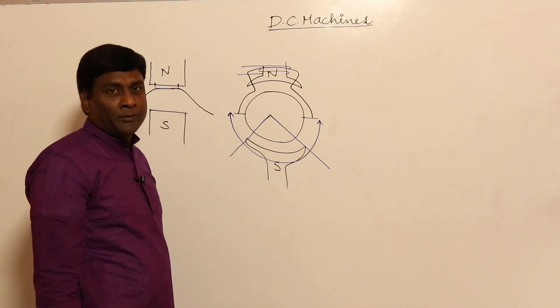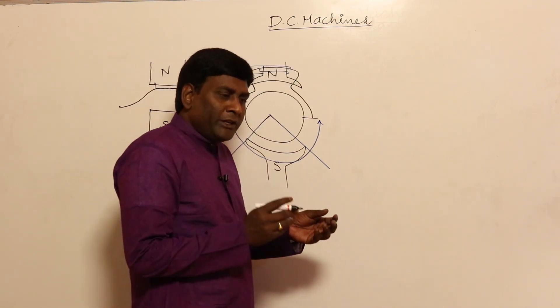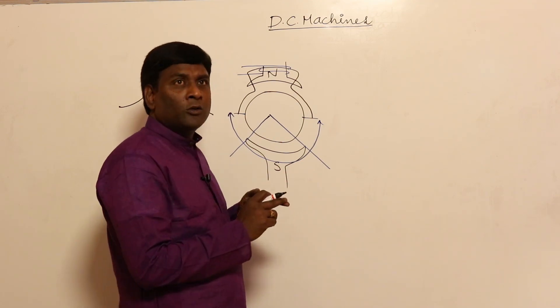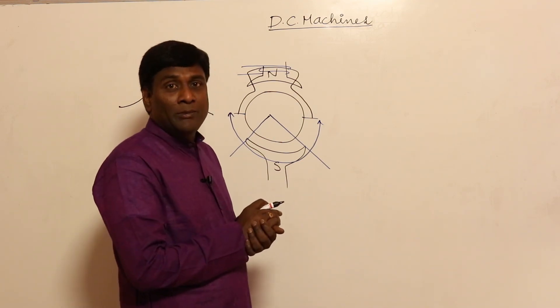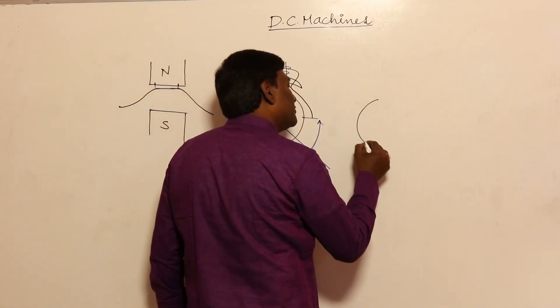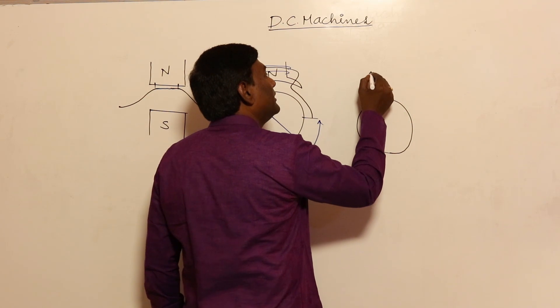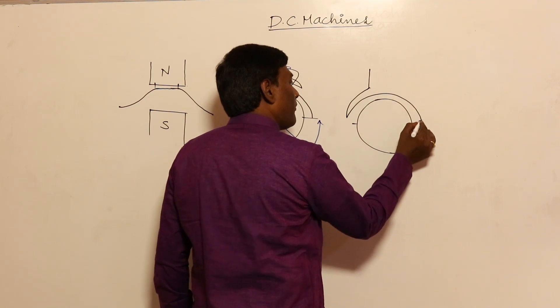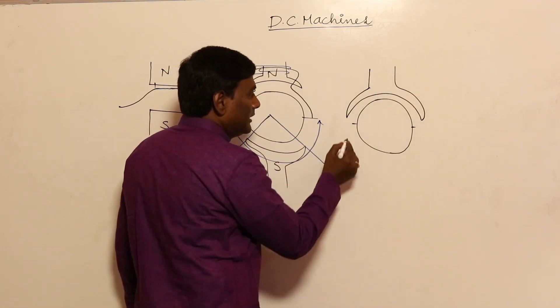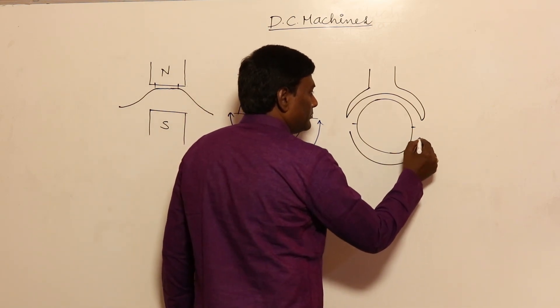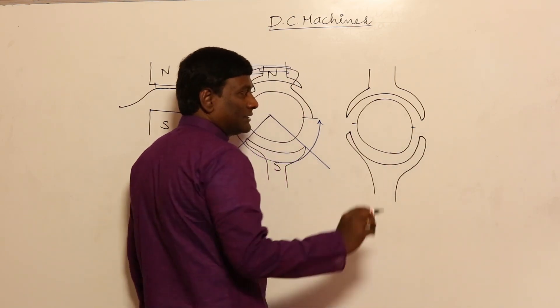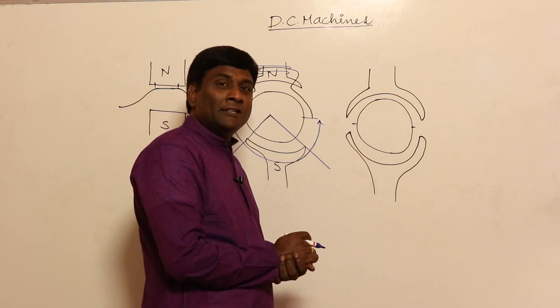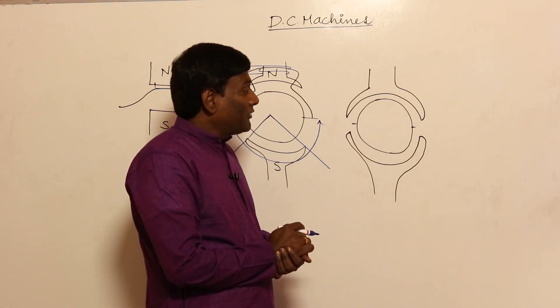Now, coming to the point: if we increase the pole arc to pole pitch ratio, what will happen? Basically, if I increase the pole arc to pole pitch ratio, the flat-topness will be increased. For example, if I have two poles like this — with this kind of wider pole — the pole arc to pole pitch ratio is increased, and so flat-topness is going to be increased.